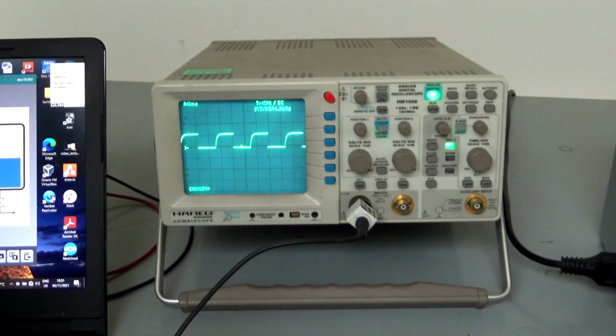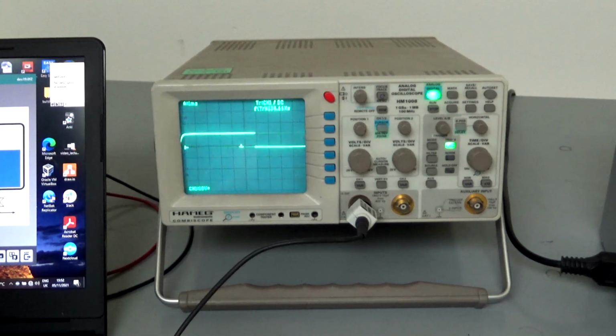On the oscilloscope, I can see almost a square signal coming out of the transducer, and the circuitry on board converts it into a continuously variable voltage between 0 and 8 volts. So by acting on my set point, now I am regulating the flow rate. And then I see the action of the PID control. And I also hear it on the pump.